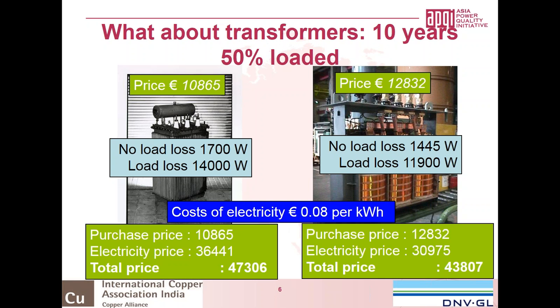If you look at both transformers and take the losses into account, you will see that within 10 years the transformer on the right side has a lower total price compared to the transformer on the left side. Basically, that's what you have to do when you compare transformers. Very easy. Don't look only at the cost of the investment, but also at the operational cost of transformers. And of course, all of you know that there is much more than only looking at the losses. You also have to maintain transformers and those kinds of things. But in this presentation, we will look at the losses of the transformer and the price, and also some CO2 emission, and how to calculate with those things.